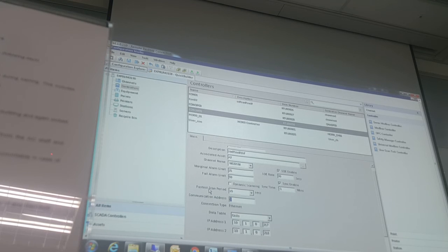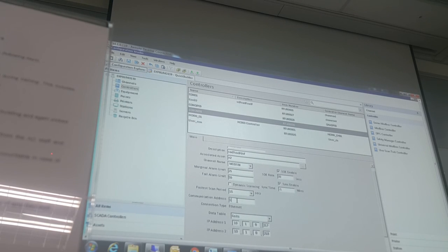What is the device ID of the SM? It is just the node number, and our node number is what? 1, right? But if you enter this number 1, you will not communicate with the SM, because Honeywell has a rule. If you want to communicate with SM using Modbus, you need to multiply the node number by 4.